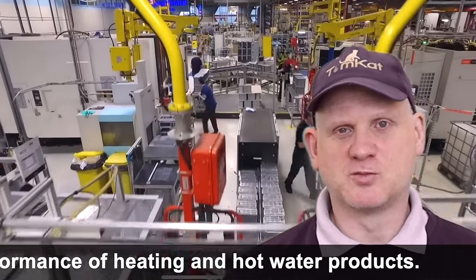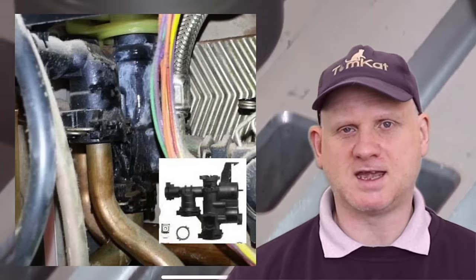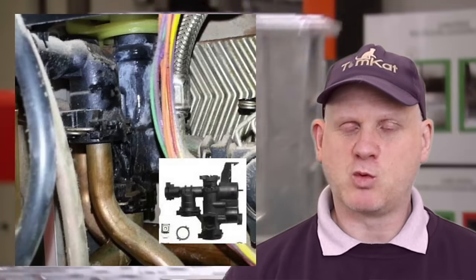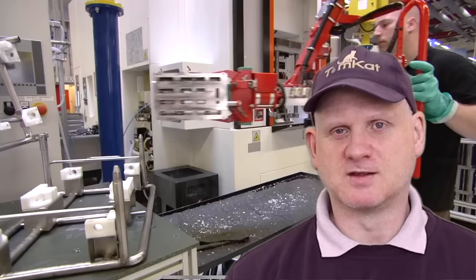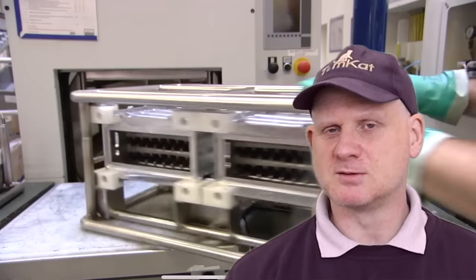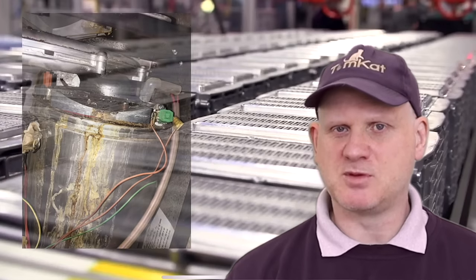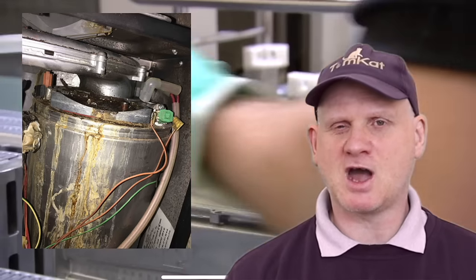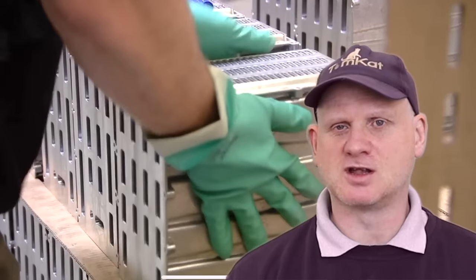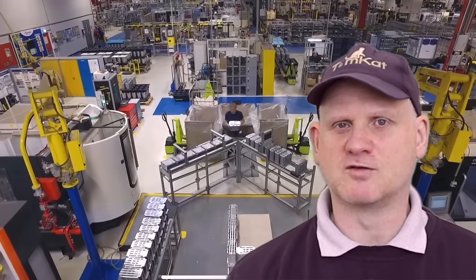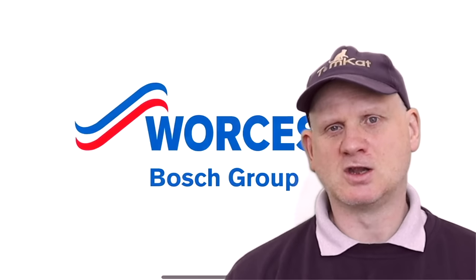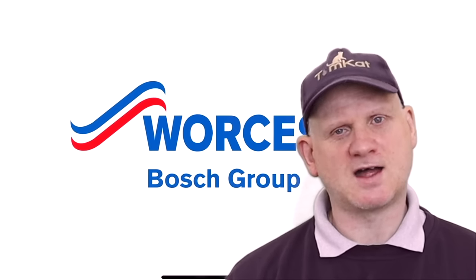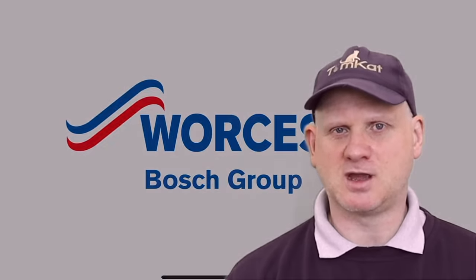The cons for the Worcester boiler: one of the main ones is breaking down and leaking on the hydro block. They are one of the most expensive boilers on the market, but parts are reasonably cheap for them. It has an aluminium heat exchanger and you have to be an accredited installer to be able to give the 10 or 12 year warranty. So that's a quick look at Worcester Bosch, who are the market leader in the UK.